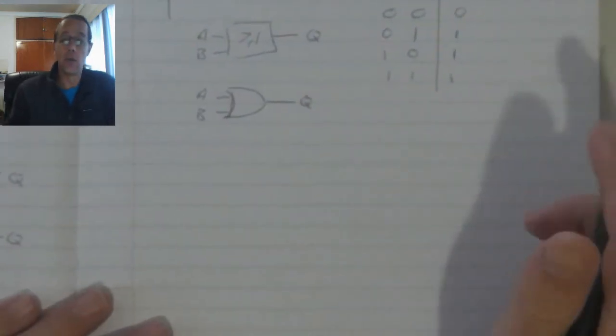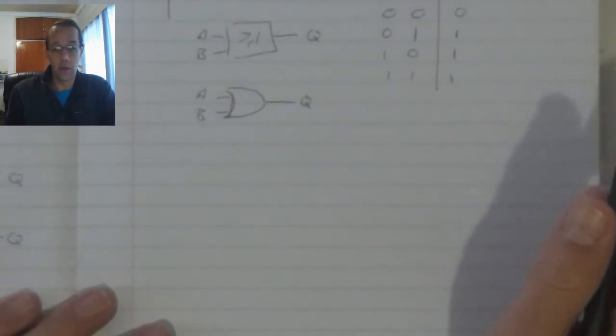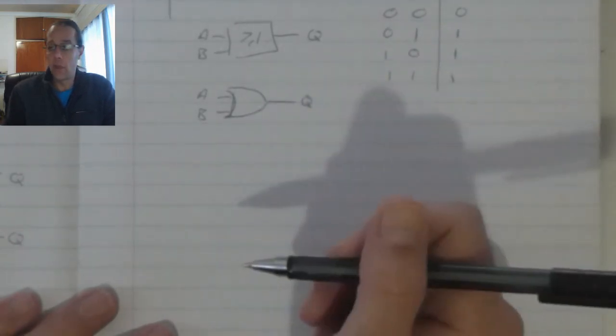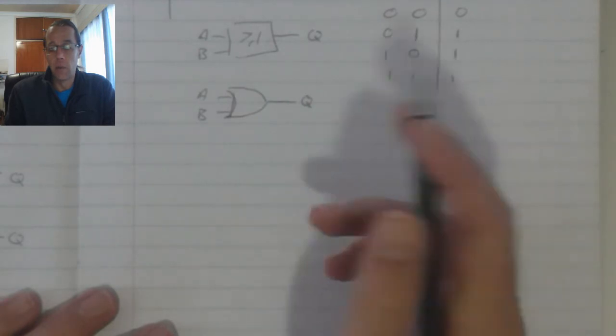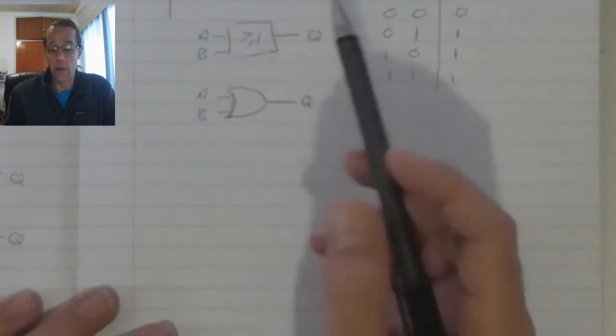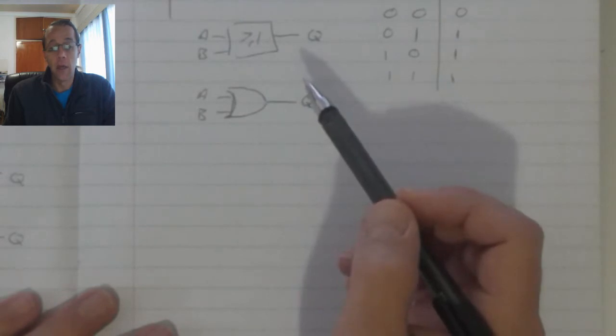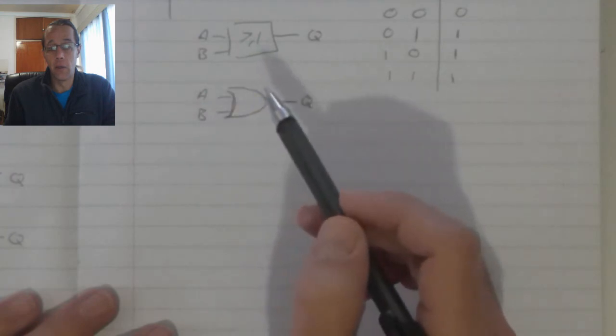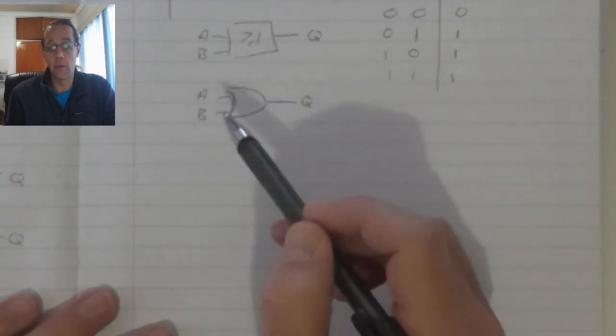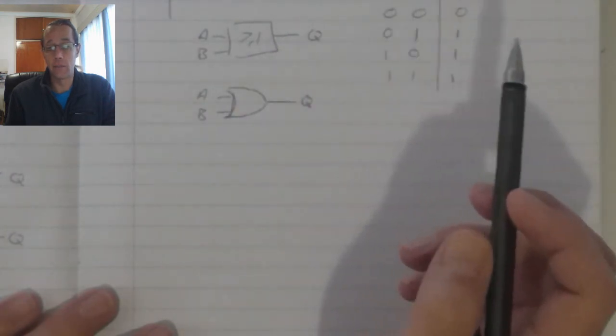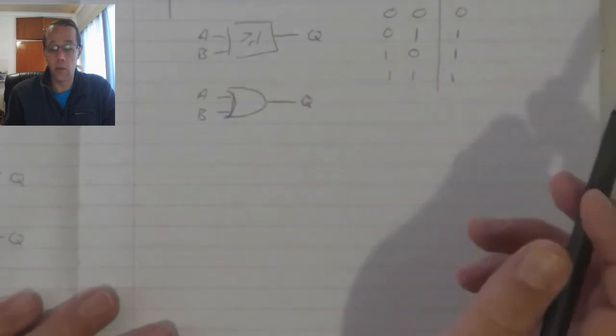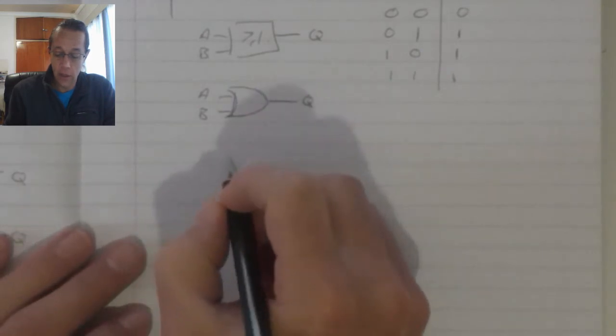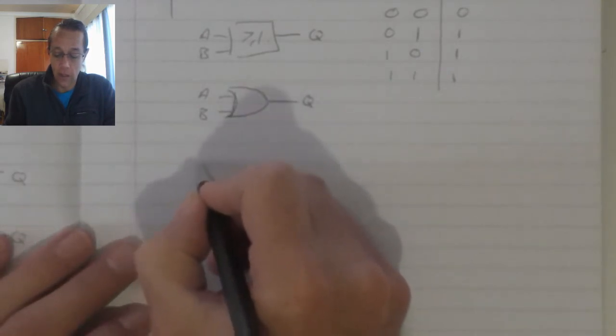Now, sometimes it is necessary to invert a function. For example, the overload. When the overload is triggered, it's supposed to turn the direct line starter off. But, let's say we want to activate or use the overload to activate an output to indicate that that is what the fault in the circuit is. So, then we use the invert function.